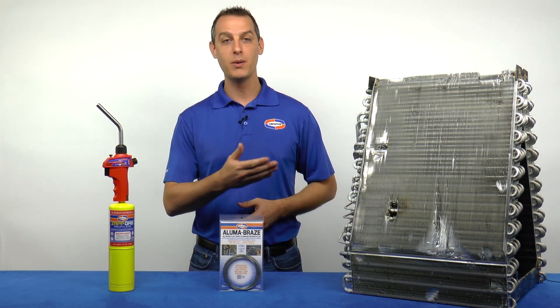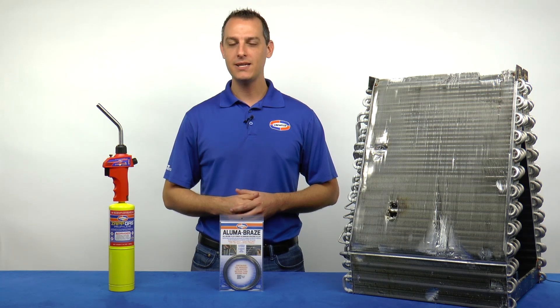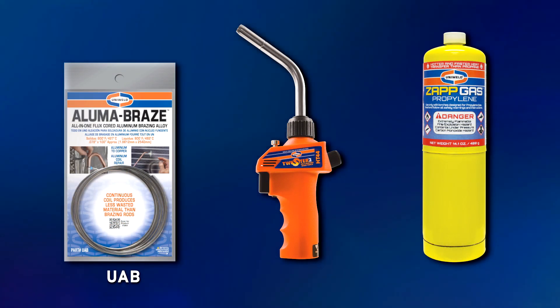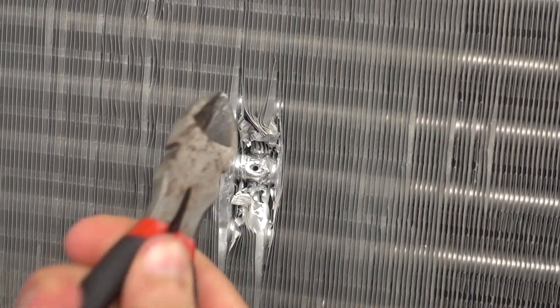I have an aluminum evaporator coil here, and I've punched a hole behind the fins. I'm going to show how easy it can be to repair this small hole using AlumaBraze along with Uniweld's HT44 self-igniting hand torch and Zapp Gas disposable cylinder. The fins have been removed to expose the hole.